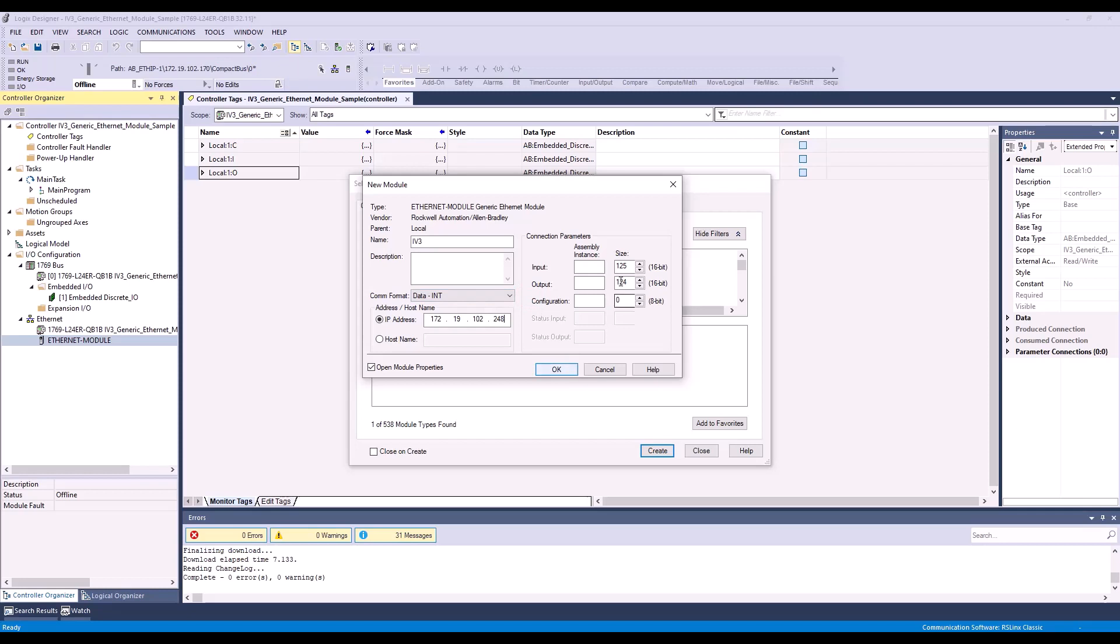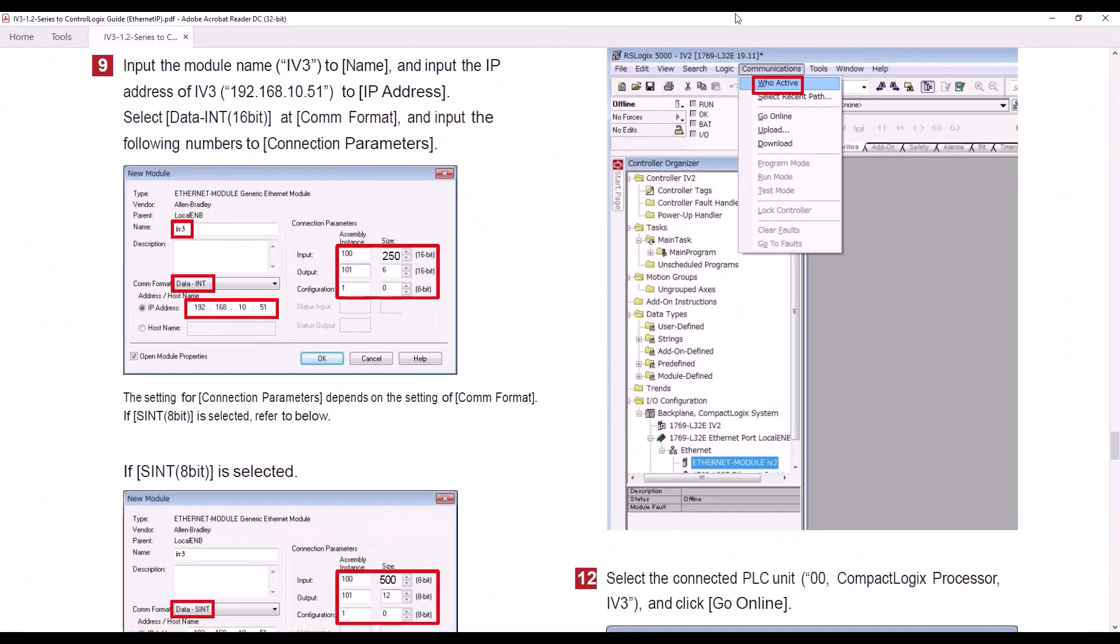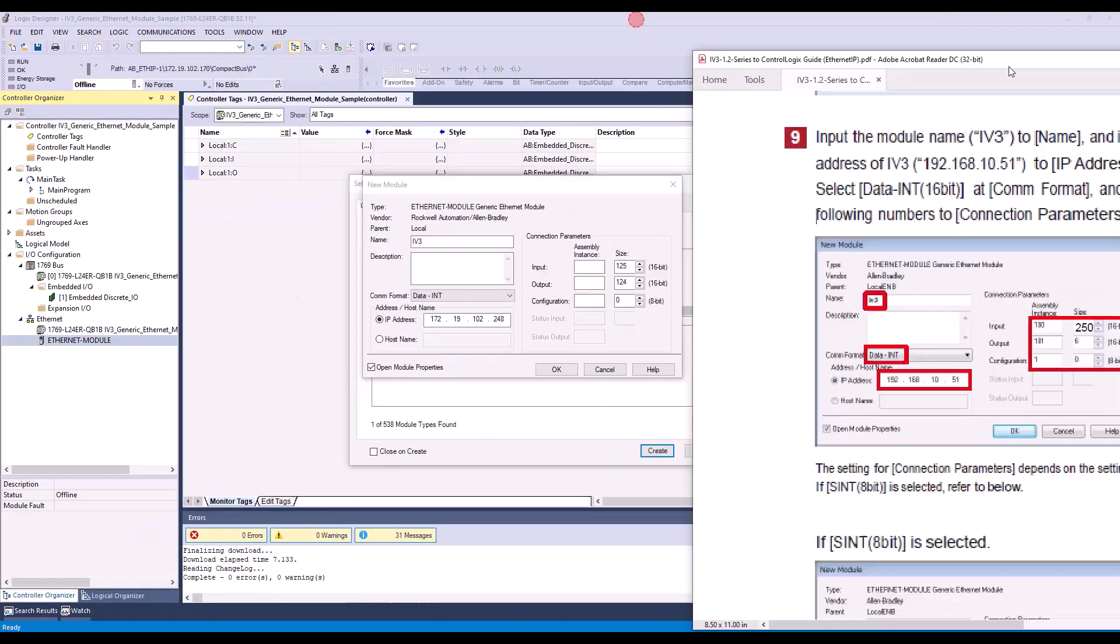And lastly, we need to fill out the connection parameters. To find these parameters, you can reference this IV3 to ControlLogix setup guide. And on page 6, step 9, it lists the parameters necessary for our integer format. So as you can see, input is 100 with size of 250. Output is 101 with size of 6. Configuration is 1 with size of 0.